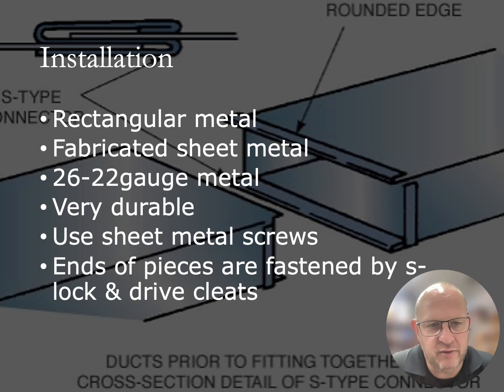So the installation of metal ductwork or rectangular ductwork, it can either be prefabbed and bought from the manufacturer, or we can take these things and actually bend up the ductwork ourselves. To save time, manufacturers have produced common sizes when it comes to the ductwork. They've fabricated the sheet metal in a certain way. One side of the ductwork has a Pittsburgh on it, and then we'll place those two pieces together to give us a nice rectangular ductwork that our airflow will go through.